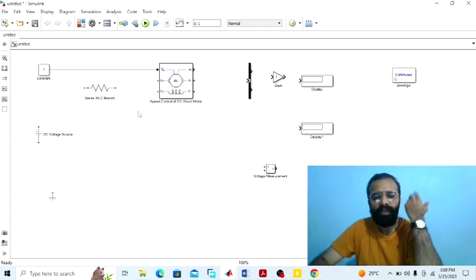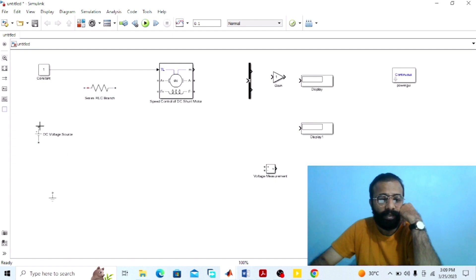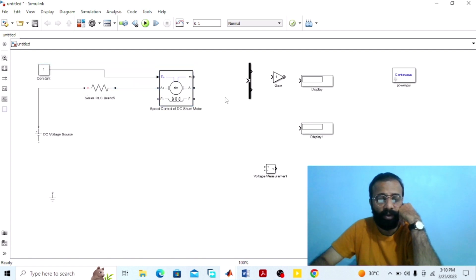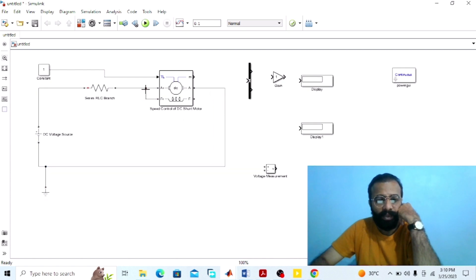According to the armature control method circuit diagram, this resistance is connected in series with the armature winding of the DC shunt wound motor, and the field winding is connected in parallel with the armature winding. Connect the DC supply in series with this armature resistance, which is connected in series with the armature winding. Connect the negative terminal of the DC shunt wound motor with the negative terminal of the supply voltage, and connect the ground with the negative terminal of the supply voltage. Now connect the field winding in parallel with the armature winding.